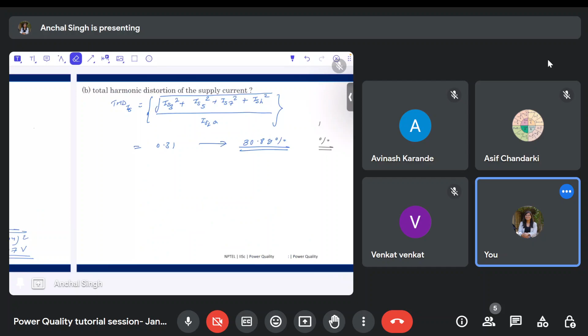So I can write here: before compensation, IS was equal to the fundamental current plus third harmonic plus fifth harmonic plus seventh harmonic plus ISH, all the components. But after compensation, IS equals IS1 only, because all these IS3, IS5, IS7, and ISH are supplied by the passive filters.